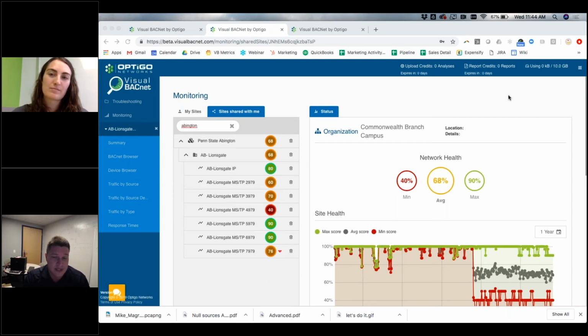One of our goals is actually to set it up so that this health score has to be above a certain number for us to pass off on the actual HVAC system. That you have to have a clean score of whatever we decide that to be. We've even looked at that on the alarming side, saying that you must be under a certain amount of alarms per 24-hour period before we're going to accept the building on the BAS side. So having this ahead of time before we go to accept has been very invaluable there.